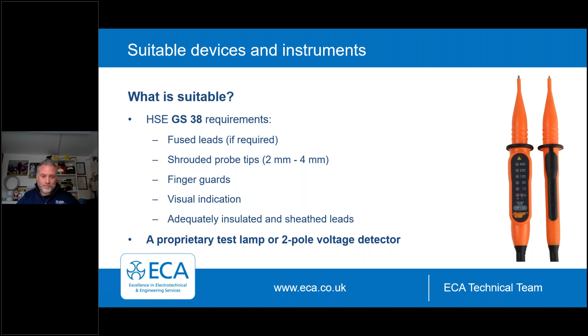Importantly, these have fused leads where required. The shrouds are protected, so you just push that into your terminals. They have finger guards, a couple on there. They have a visual indication with LEDs which will light up. Importantly, there's no batteries in these to go wrong, so it just works - if there's voltage present it will tell you, if not the lights remain off.